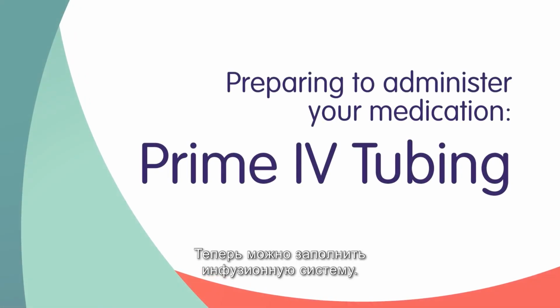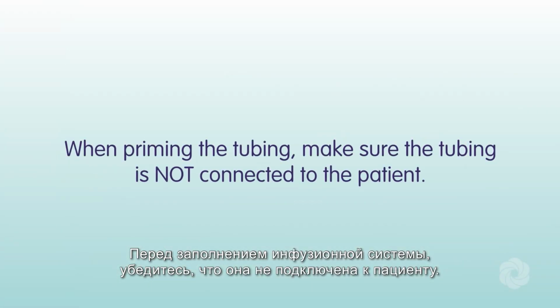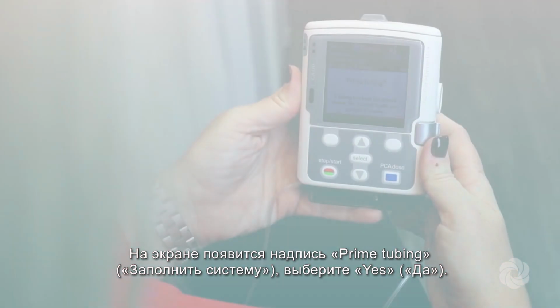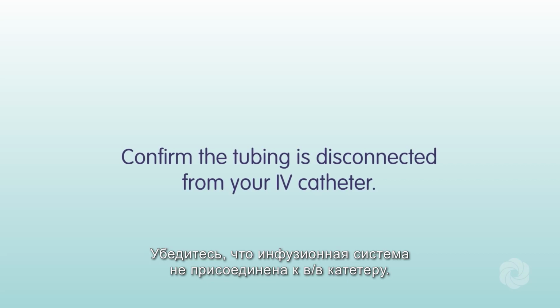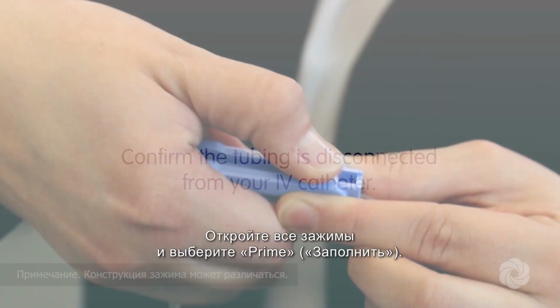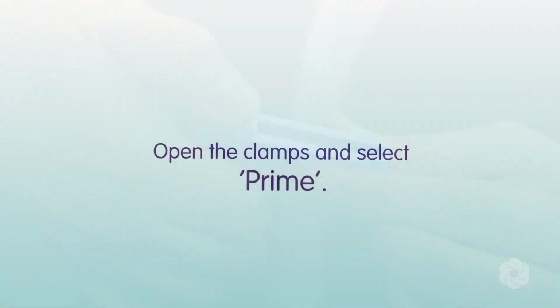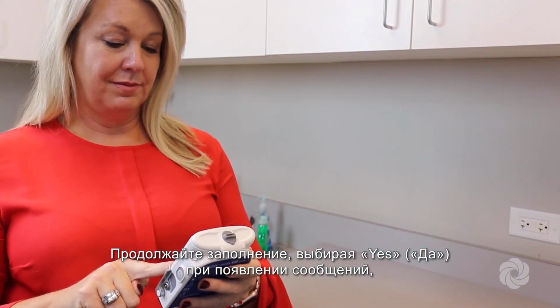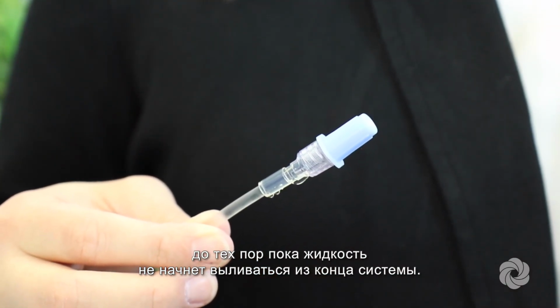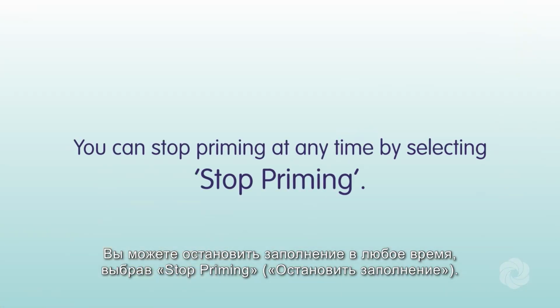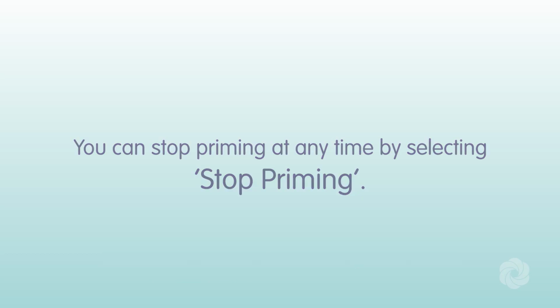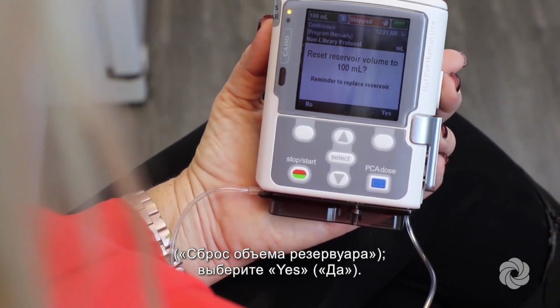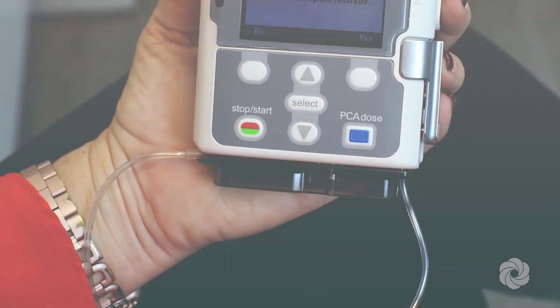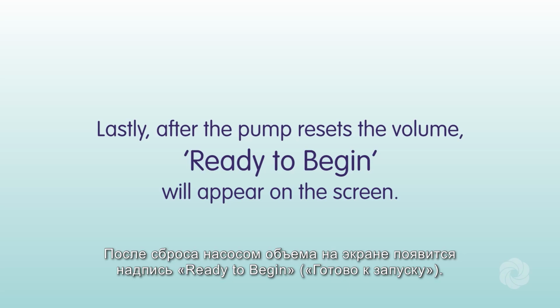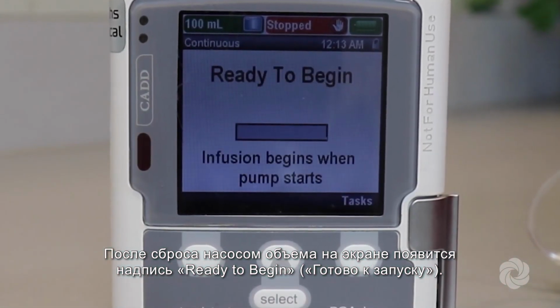You are now ready to prime your IV tubing. When priming, make sure the tubing is not connected to the patient. Prime tubing will appear on the screen. Select Yes. Confirm the tubing is disconnected from your IV catheter. Open the clamps and select Prime. Continue priming by selecting Yes when prompted until fluid drips from the end of the tubing. You can stop priming at any time by selecting Stop Priming. Reset reservoir volume will then appear on the screen. Select Yes. Lastly, after the pump resets the volume, Ready to Begin will appear on the screen.